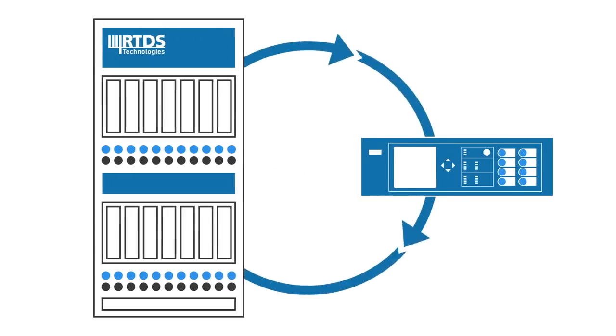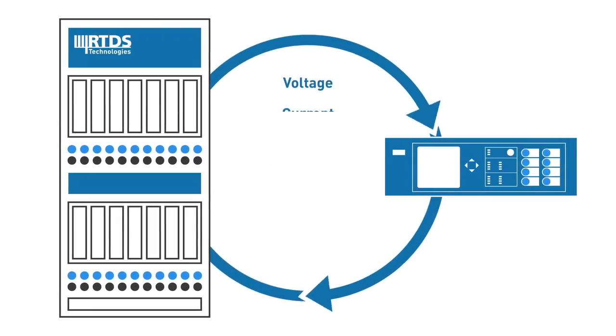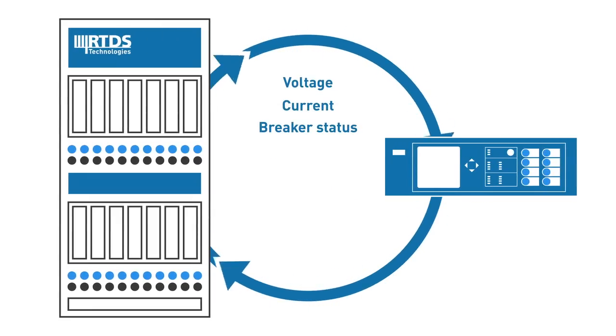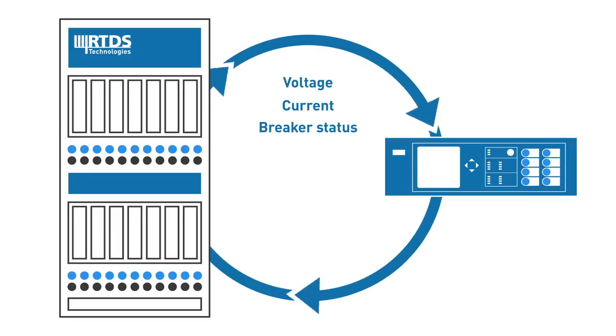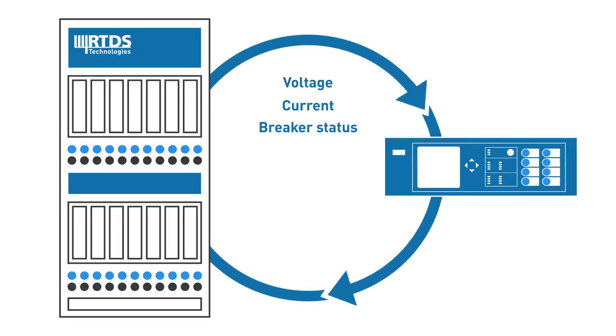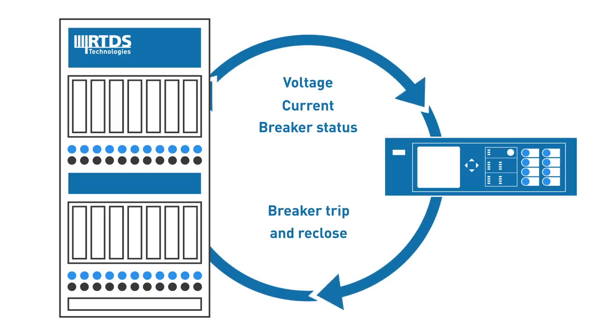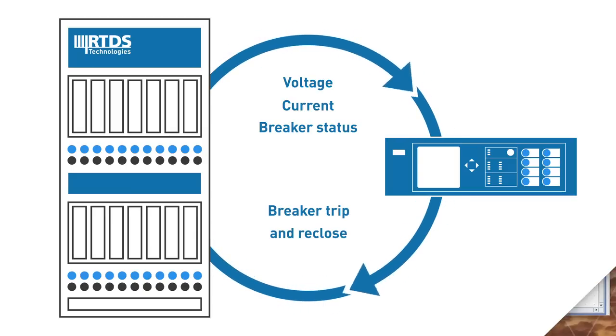In this demonstration, we will send line voltages and currents as well as breaker status from the simulation to a physical relay outside of the simulation. We will connect breaker trip and re-close signals from the physical relay back into the simulation to close the loop.